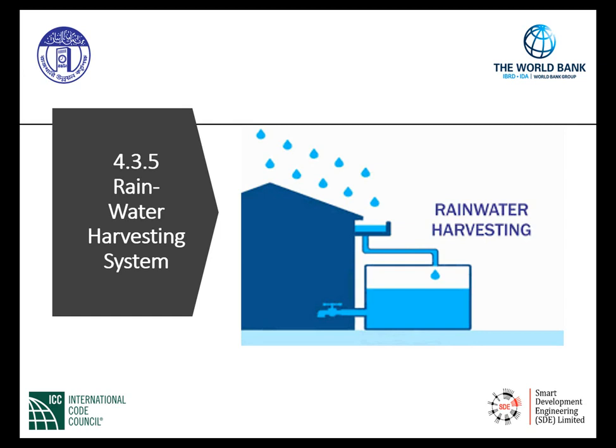Section 4.3.5 deals with rainwater harvesting systems. This lets us know that when we have a building that is more than 4,000 meters square, it is going to have its own rainwater harvesting system. So it does tell us the rainwater harvesting system is going to be done in accordance with Chapter 7, Part 8. But it tells us here, if you're over 4,000 meters square, you have to have this rainwater harvesting system. And the only other thing it gets into is how to size the capacity of that reservoir, and a couple minor things. The rest of it sends us over to Chapter 7, Part 8 to see how it needs to be installed. We're not going to jump over there right now because I want to try to stay in this energy chapter as much as possible, but we definitely are going to talk about Chapter 7, Part 8 here in a little bit.